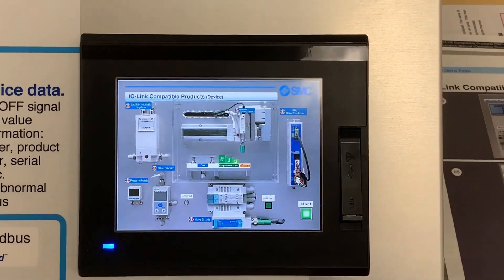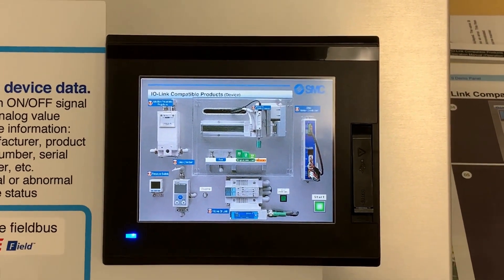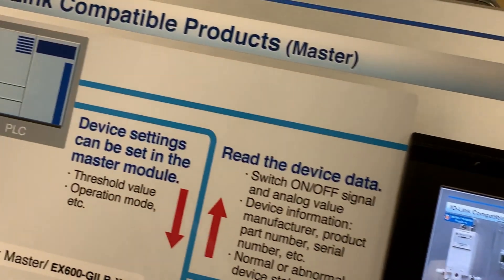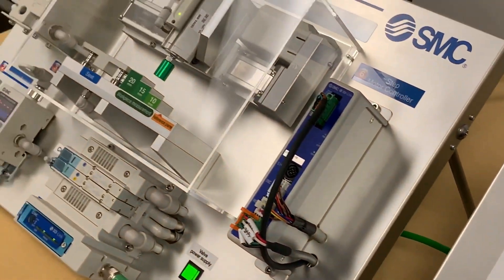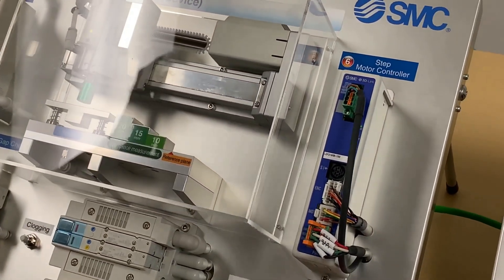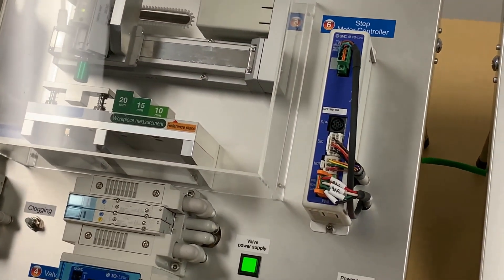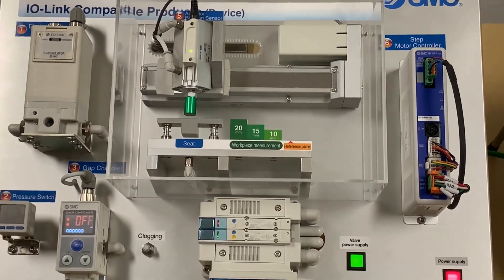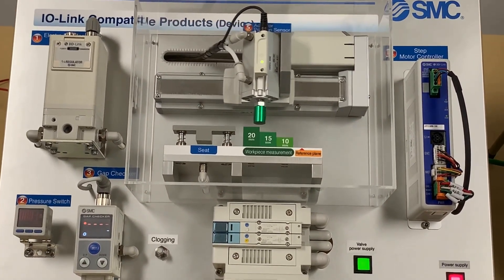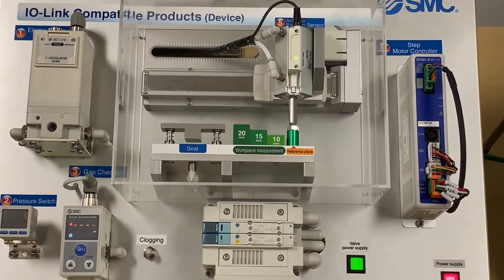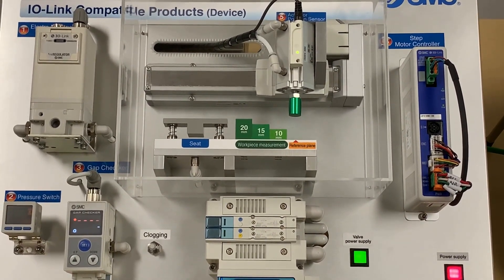The advantage of this is: one, you can communicate all the data; two, you can control all the data; and the third most important thing is that it is used for diagnosis. So when something is going wrong or probably something is on the decline — probably three or four months down the line — and you see the performance of the sensor or the actuator is going down, or there is something going wrong with the pressure, you can see that the values are declining. With which you can predict that it will probably fail in a couple of months. So this is a very good tool for maintenance, for prediction, and also for control.